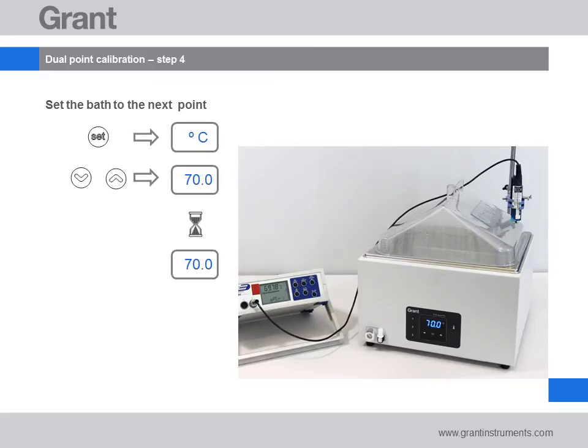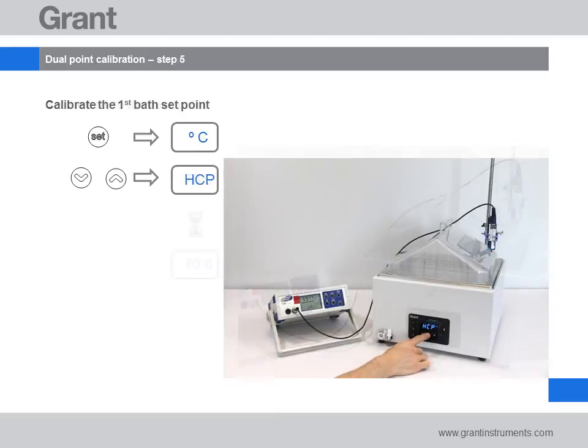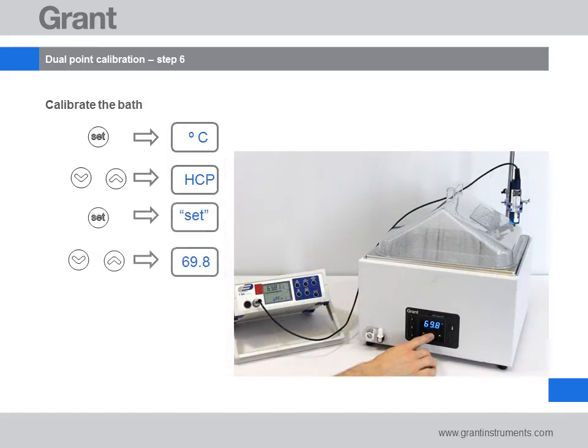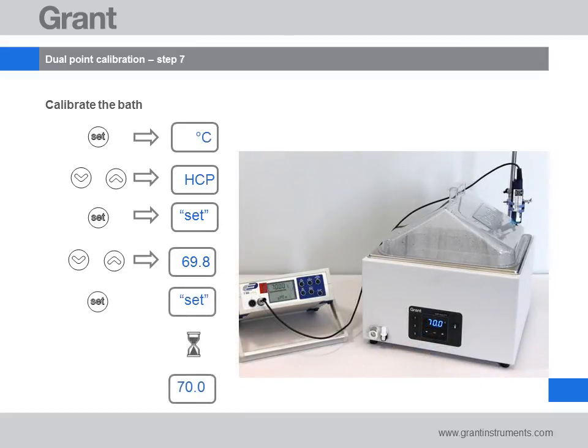Now set the temperature of the bath to the required upper calibration point, in this case 70 degrees C. Allow the bath to stabilise at this temperature. To do this, press the Set button and, using the up and down keys, navigate to the screen displaying HCP. Press Set and then enter the reference thermometer value using the up and down keys. Press Set to enter the value and wait for the bath to automatically adjust to the set temperature. This now completes a dual point calibration.